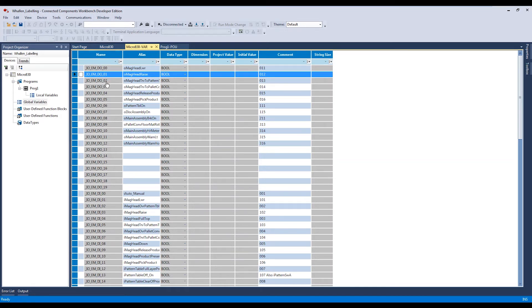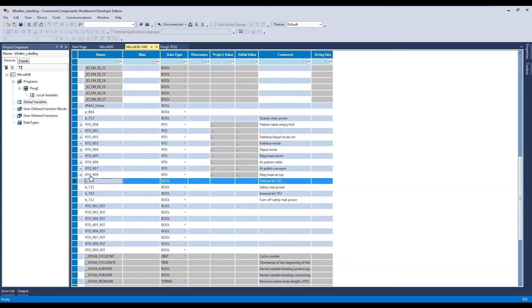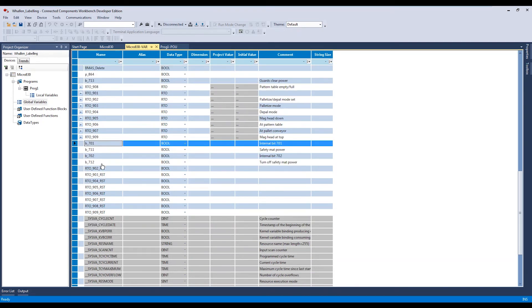Like in other programming applications, you can add programs and routines, and there are global variables. The IO variables - _IO_EM_DO_00, 01, 02 - represent all built-in IO in this PLC, where DO is digital output and DI is digital input. These are the addresses we wrote down on the spreadsheet. In the comment field we noted what they used to be for ease of debug.